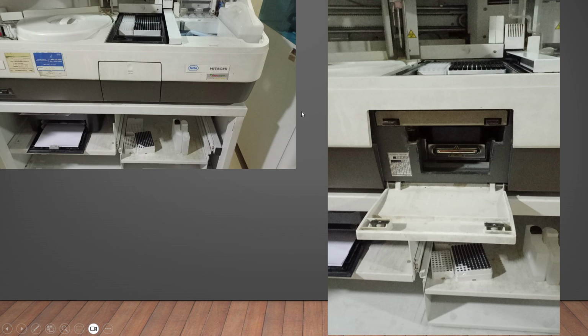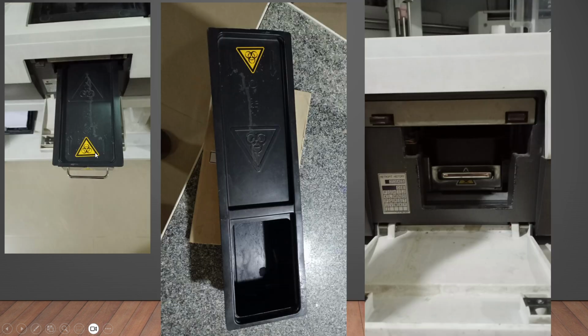Okay, so this is the solid waste area. When you press this, it will open like this, but do remember this also has a sensor. So don't try to open this when the instrument is working. When you press it, it will open. They are magnetic, so you pull this out, and it comes out. Inside this, there is a plastic container in which everything is thrown by the instrument. But on this there is one plastic item attached, which we have removed, because many times while shaking it becomes a problem. This also has a sensor, so if it is not there, it becomes a problem.